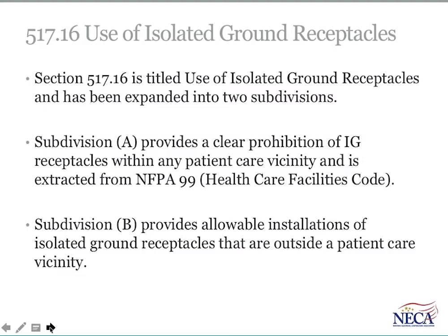Subdivision B provides the requirements for isolated ground receptacles and installations outside of that defined patient care vicinity. So that's the major change here in 517.16, to clarify that you can install isolated ground receptacles and circuits in a healthcare facility. You just can't install them within a patient care vicinity, which is a defined, dimensioned location around the nominal patient bed location.